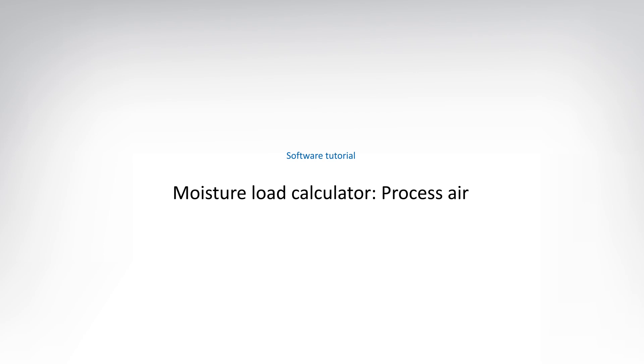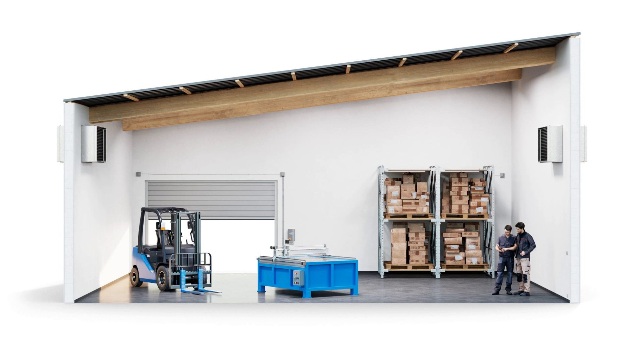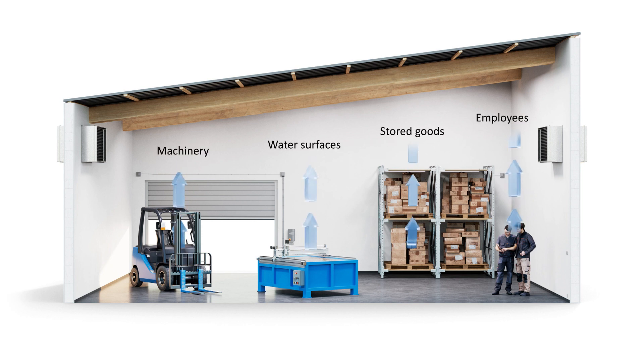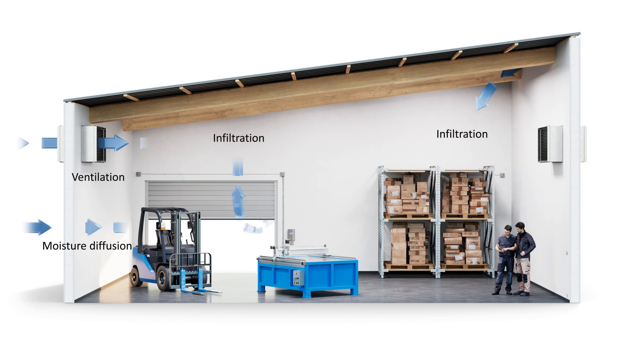Condair Moisture Load Calculator. The purpose of this video is to show you how to calculate the moisture load in an enclosed space, such as a basement or high bay warehouse. In order to find an energy efficient and appropriately sized dehumidification solution, it is essential to precisely determine the moisture load. Numerous internal as well as external moisture sources must be taken into account in the calculation.